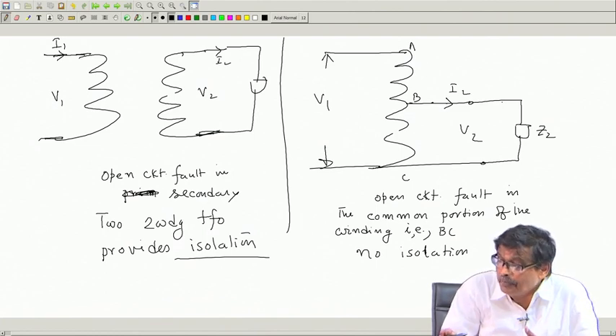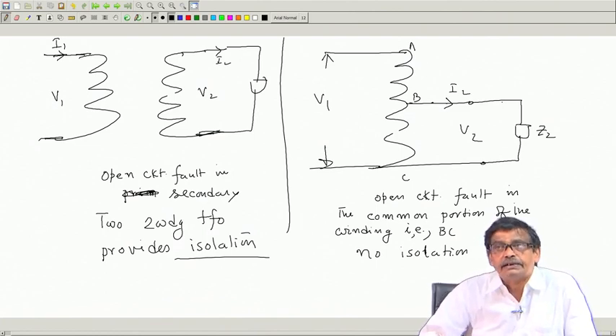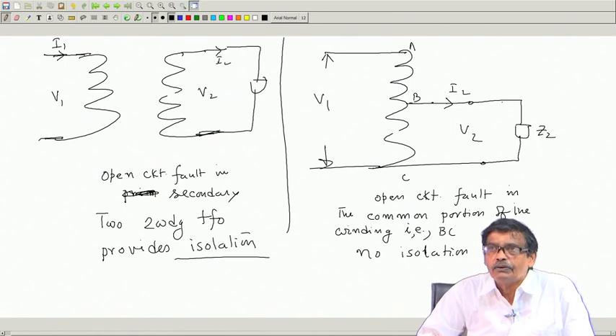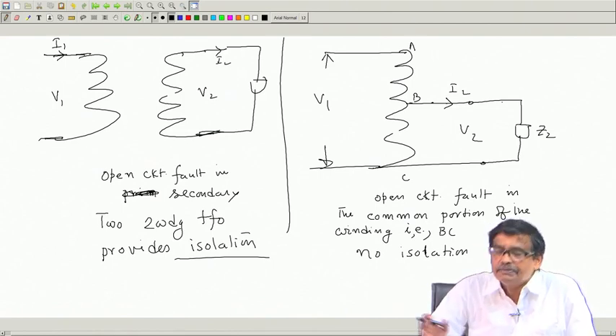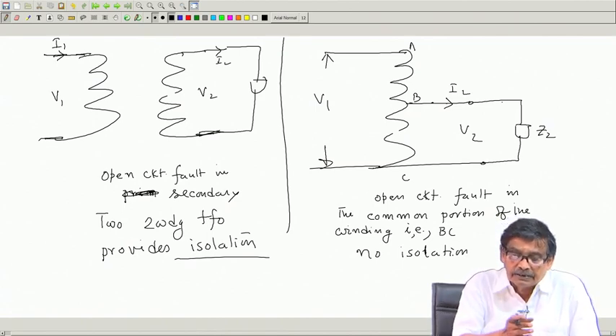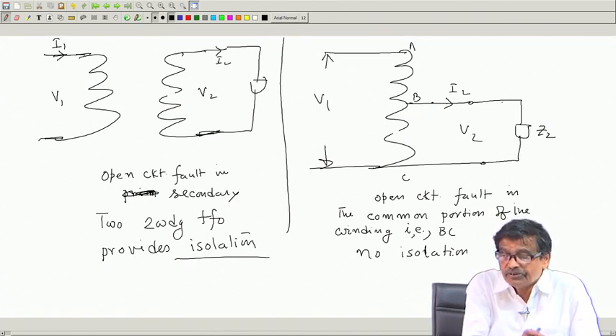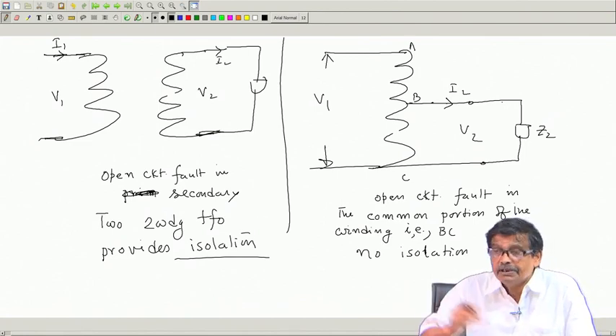This happens in case an open circuit fault takes place in the common portion of the primary and secondary winding. Therefore, an auto transformer gives you copper saving, no doubt, but it will never be able to give you proper isolation between the source side and the load side. The load may be critical, and you cannot just apply high voltages to it.